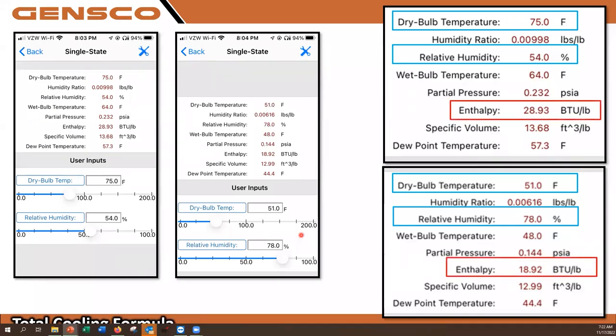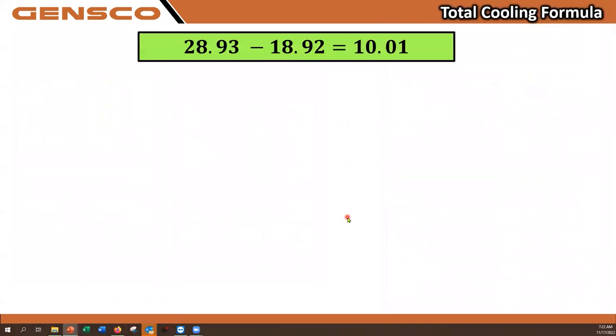And my enthalpy, or the BTUs per pound, return air, 28.93, enthalpy of the supply air, 18.92. I'm going to subtract the supply air from the return air, and I am going to come up with a delta H, or change in enthalpy, of 10.01 BTUs per pound of air.